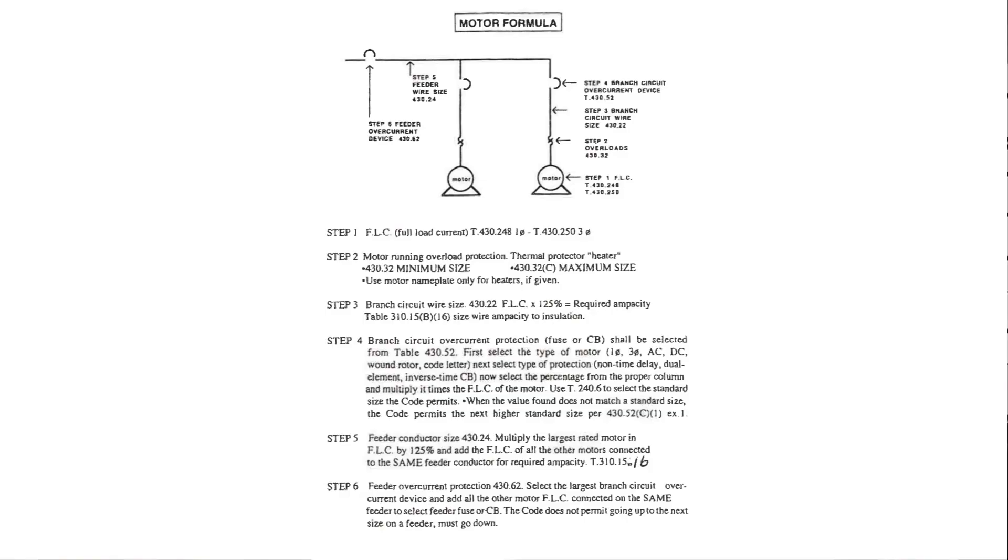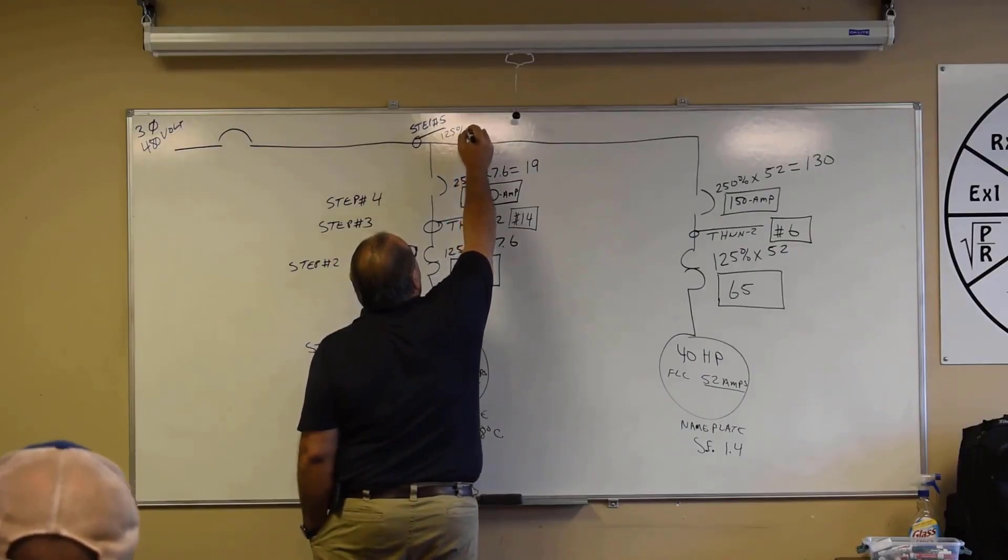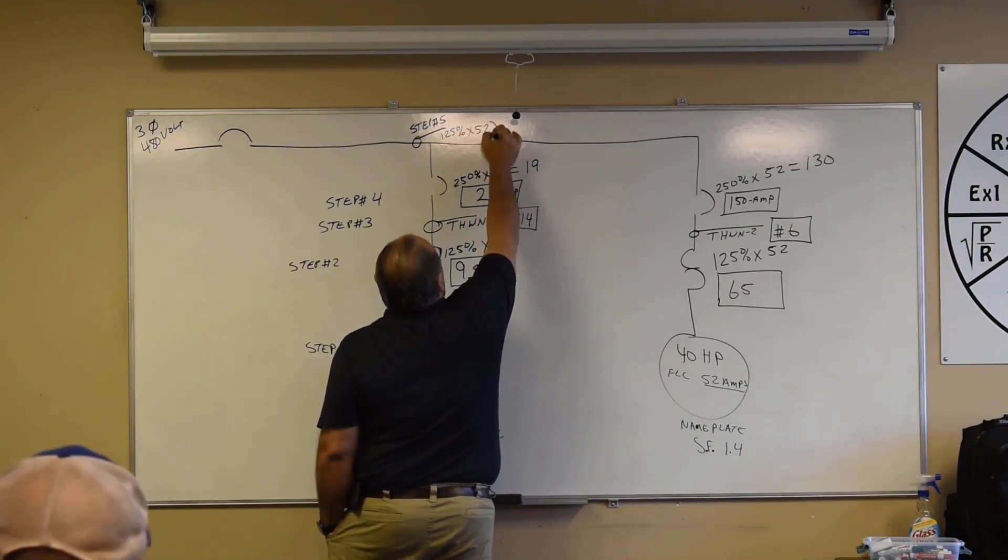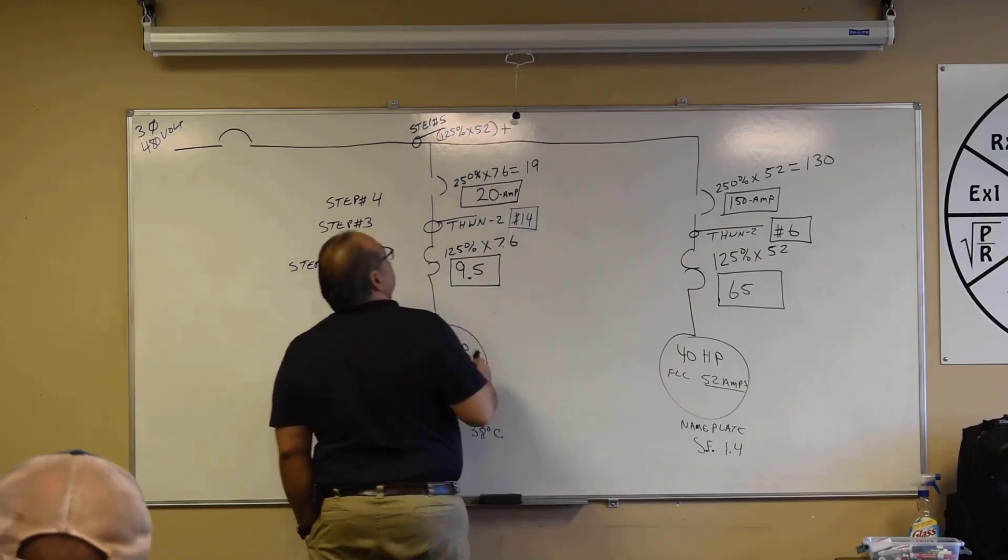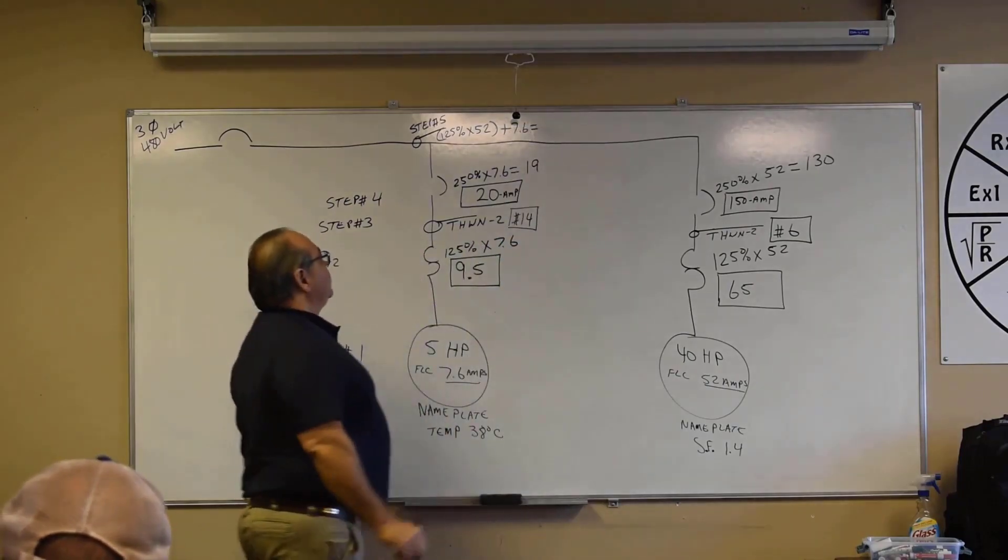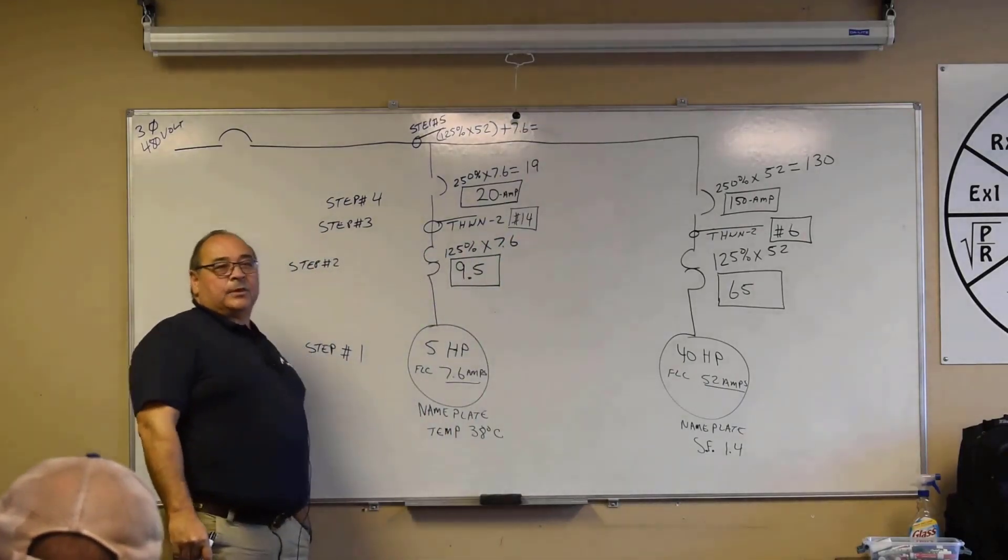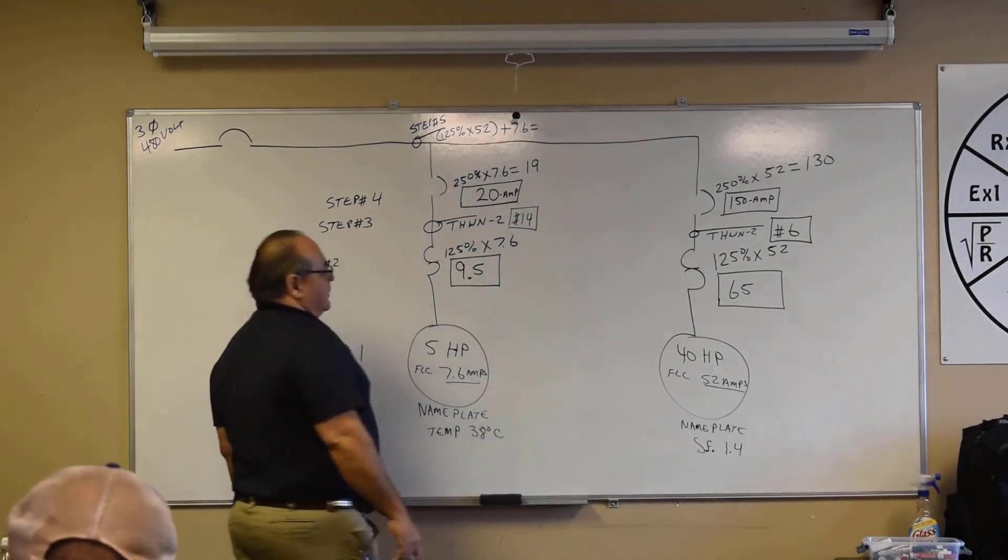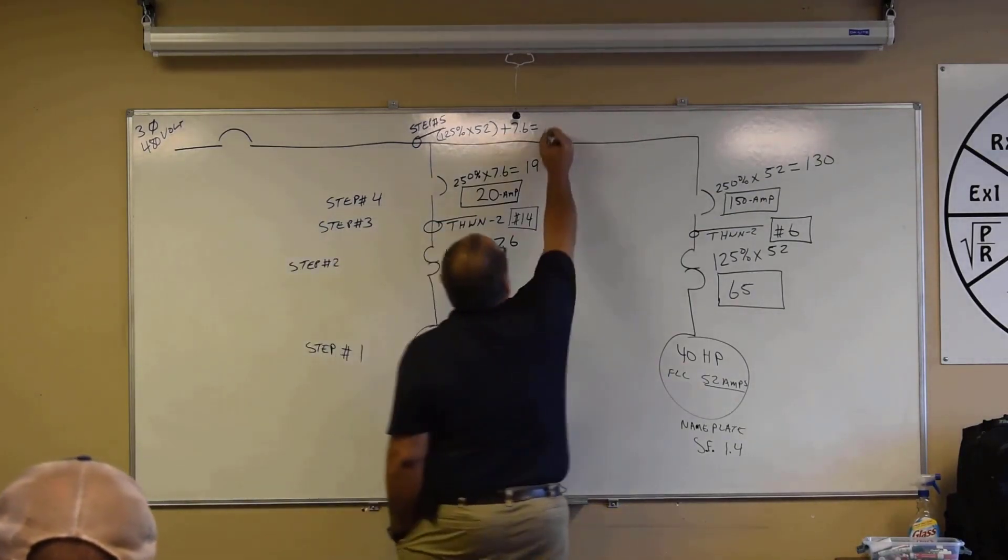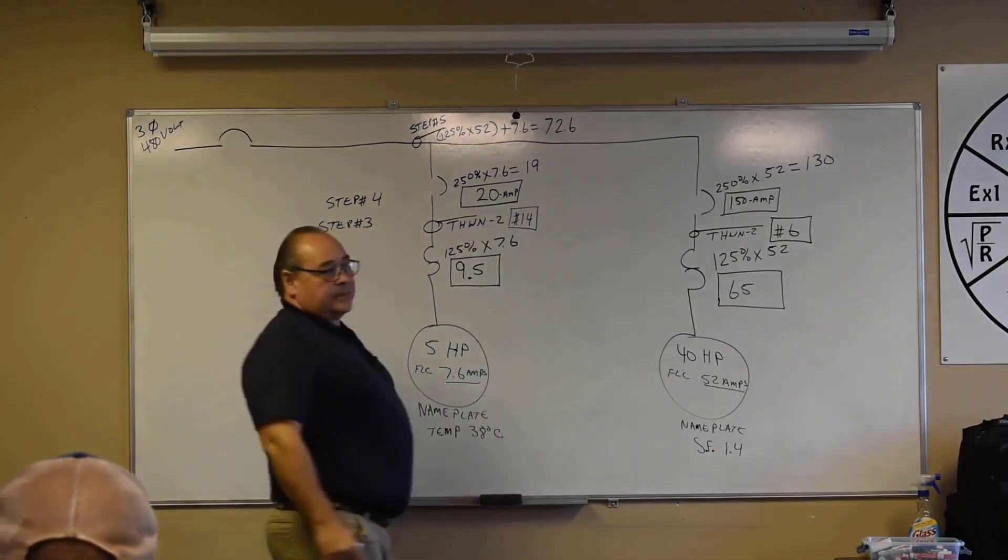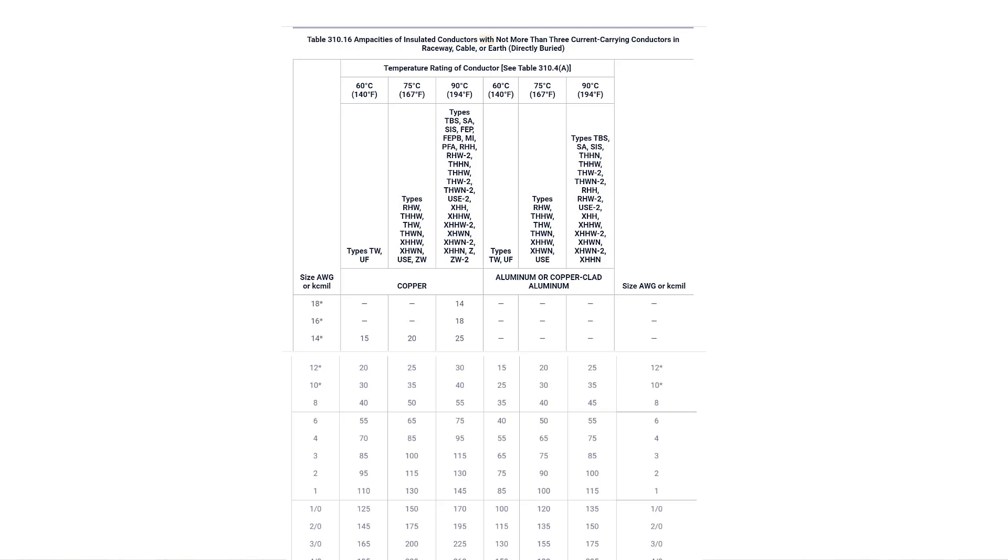So this feeder conductor size up here, step number five, right, that feeder conductor size tells us to do what? Our number five format, 125 percent of largest, which is going to be what? 52 amps, right? And then plus all others. And all others equals 7.6. So that'd be the way it looks. So 52 amps times 125 percent, what is the sum of that? We've done that once, right? 65 plus the 7.6, right? Okay, what's that equal? 72.6. Okay, so we need a wire good enough for 72.6 amps. What wire size would that be?